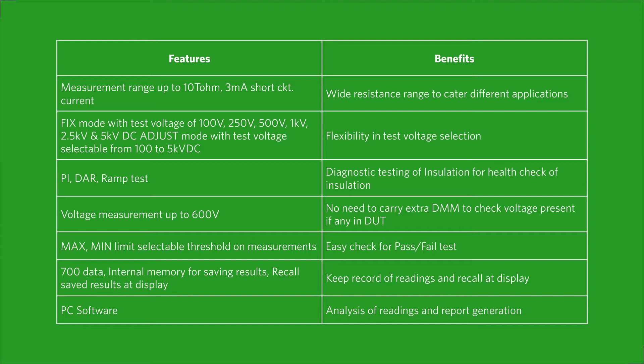PI, DAR, and ramp test for diagnostic testing of insulation for health check of insulation. Voltage measurement up to 600V — hence there is no need to carry an extra DMM to check voltage present in the DUT.